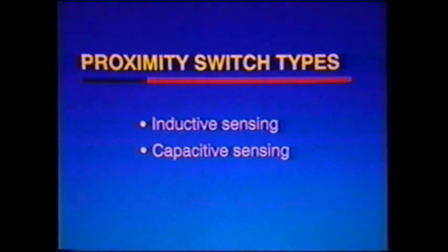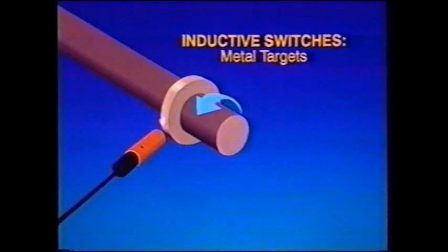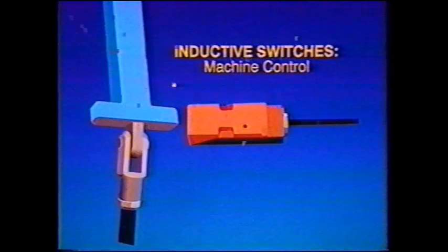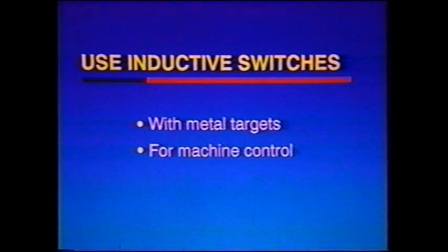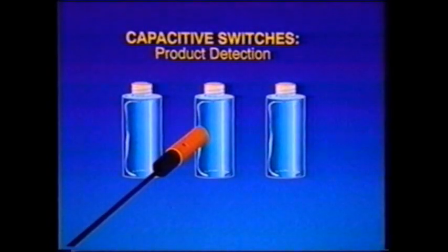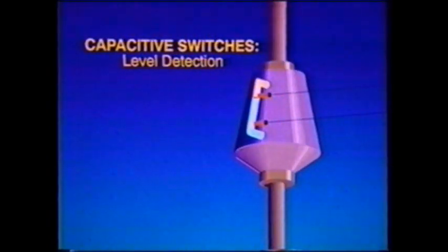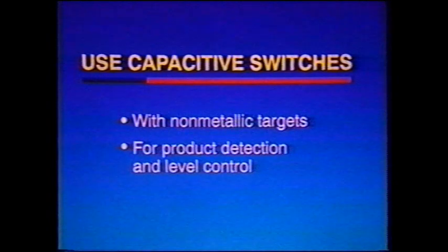This seminar is going to cover inductive sensing and capacitive sensing, the two most common technologies. Inductive switches sense metallic or other conductive materials, normally in machine control applications. Inductive switches should always be your first choice with metal targets in machine control applications. Capacitive switches, on the other hand, can sense non-metallic objects. They should be used for product detection and for level detection of liquids and granular solids. Choose a capacitive switch for non-metallic targets and for product detection and level control applications.